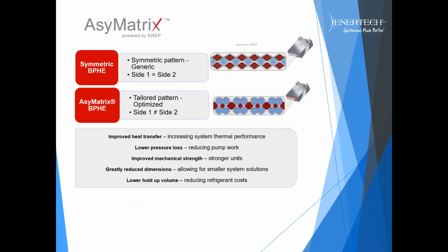And here's the asymmetrical design. If you look at the two graphics there, you have a symmetrical design, in which the water passages and the refrigerant passages are of equal size. And then you have the asymmetric braze plates, in which, if you notice, the water passages, the blue, are much larger than the refrigerant passages. And that allows us, number one, to increase the thermal performance, reduce the size, and reduce the overall head pressure on the pumping side, but it also improves the mechanical strength. So SWEP actually went through a very extensive freeze testing procedure with this braze plate.